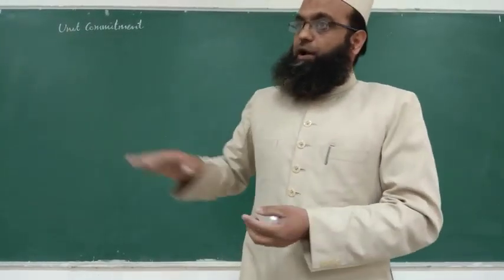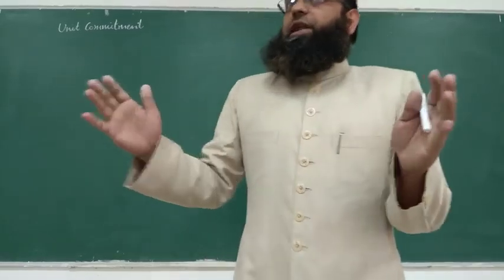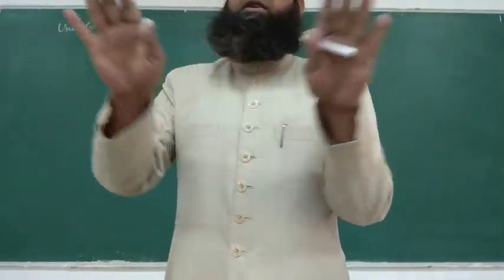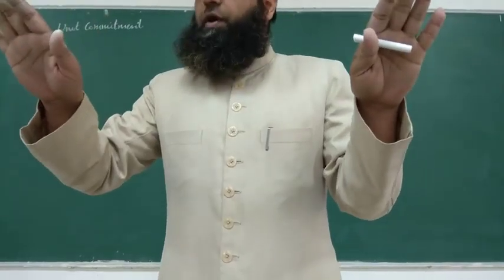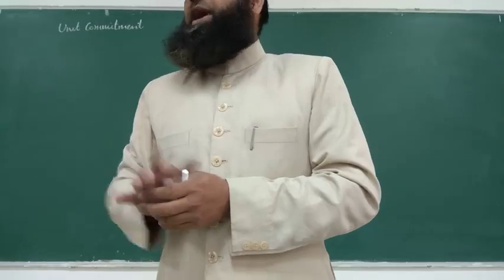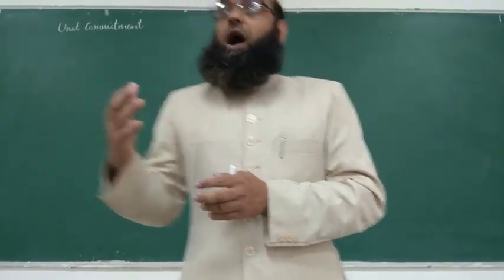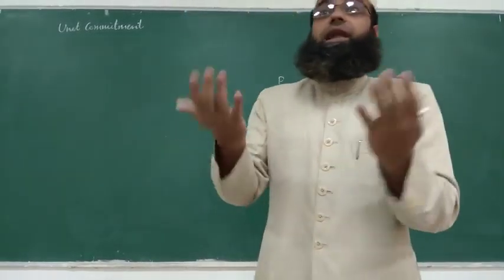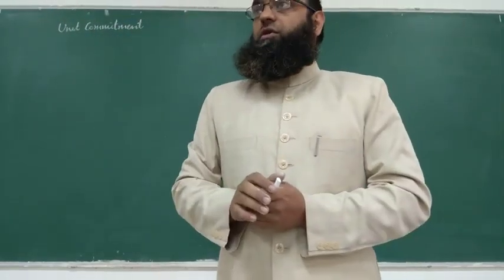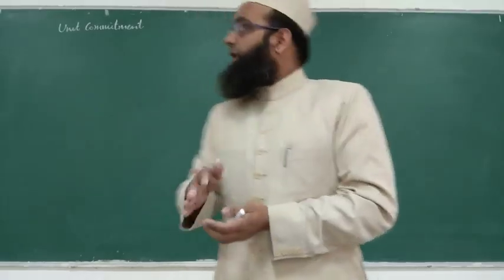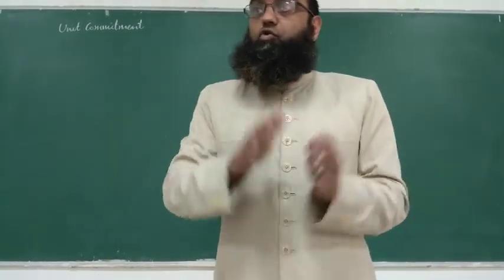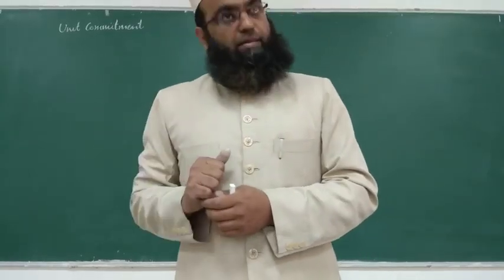So what you did till now, already selected units were given to you. These are 2 units, with corresponding characteristic equations or curves you know. So you have to load these 2 units optimally. That part is over. But how were these 2 units selected among 10 units or the total available number of units? So this task comes under unit commitment: the combination of units to be committed to meet a particular demand.